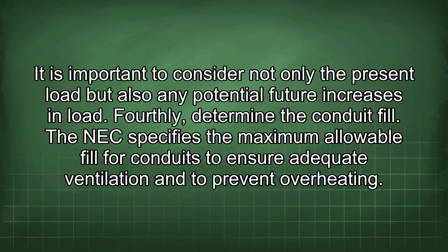Thirdly, evaluate the load requirements. The size of the conductors within the conduit must be adequate to carry the anticipated load. It is important to consider not only the present load but also any potential future increases in load. Fourthly, determine the conduit fill. The NEC specifies the maximum allowable fill for conduits to ensure adequate ventilation and to prevent overheating. The conduit fill is the percentage of the conduit's cross-sectional area that is occupied by conductors.